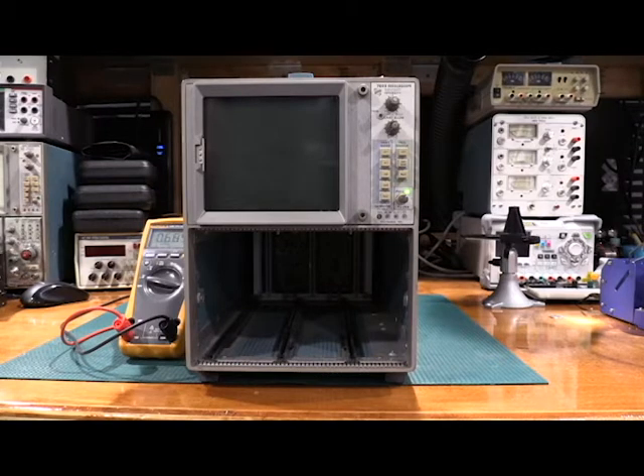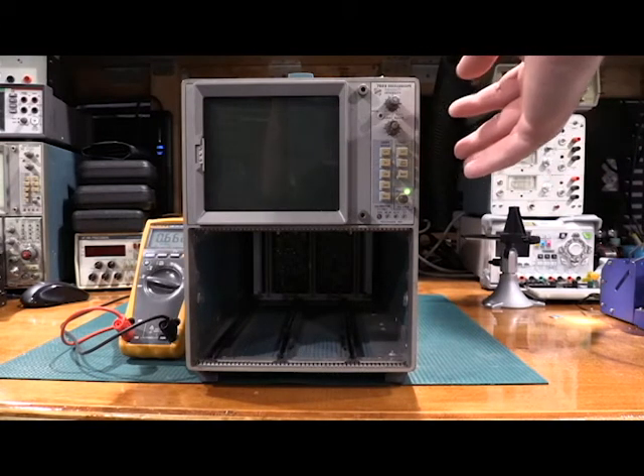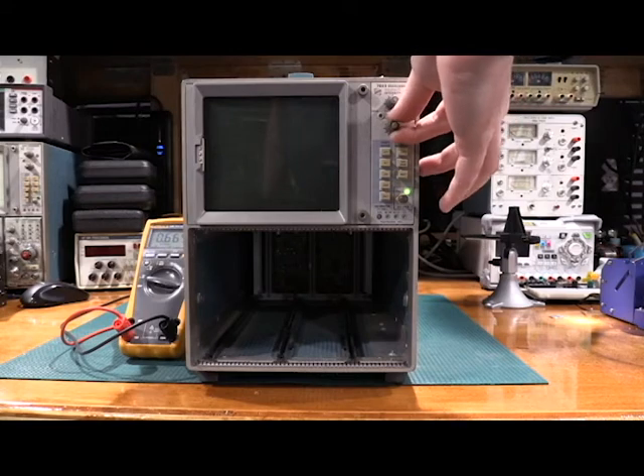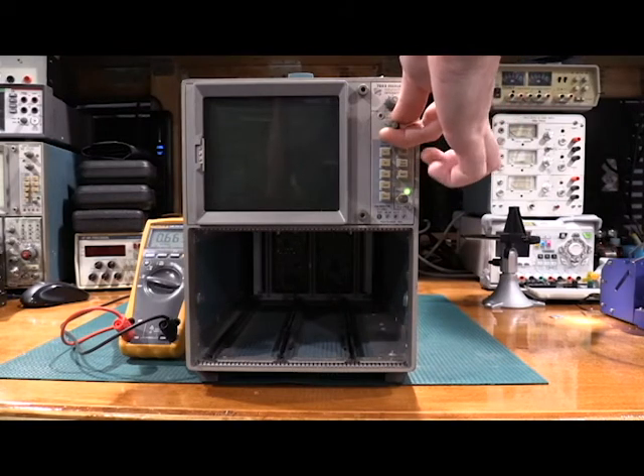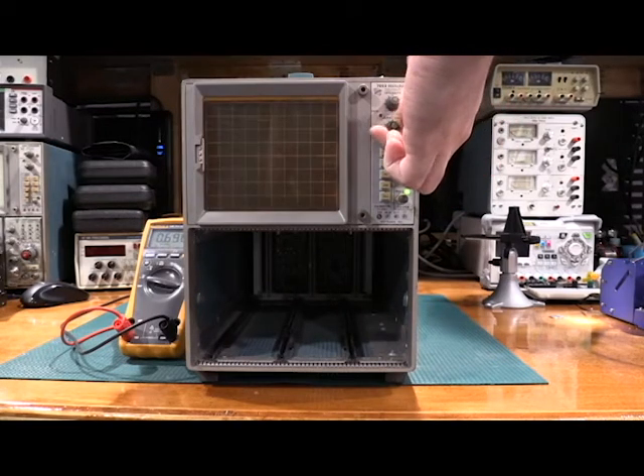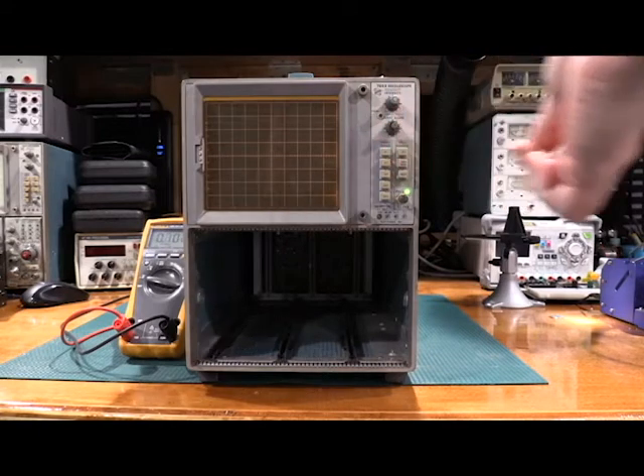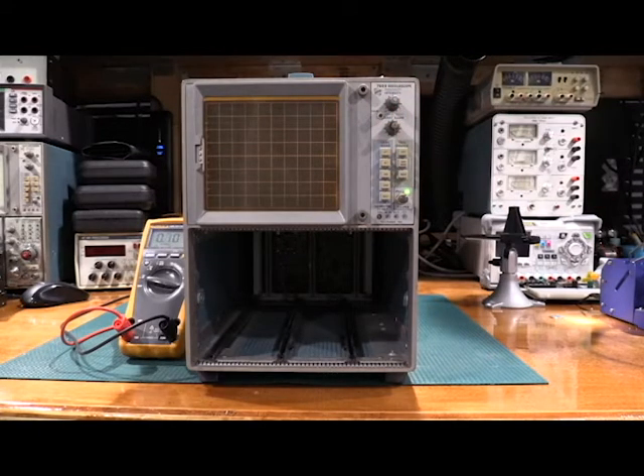It's come up. The bulbs are glowing a little bit, but they're not showing a short. And it only shows that I'm drawing 0.6 amps, so 600 milliamps, which is fine. Also no smoke, which is good. Okay, so the graticule lights are coming on, which means the power supply is at least waking up.